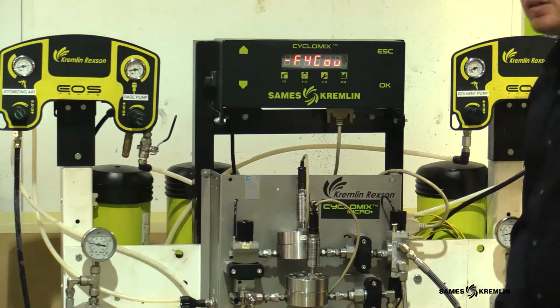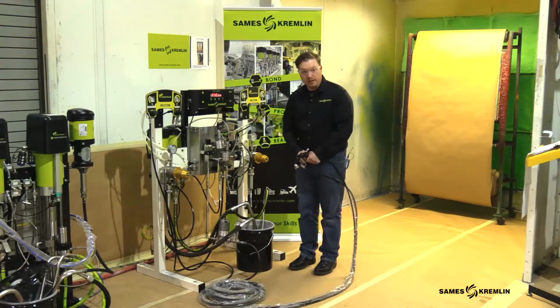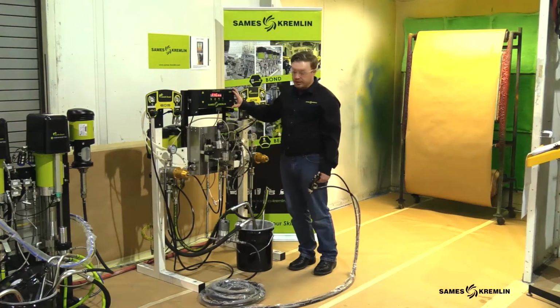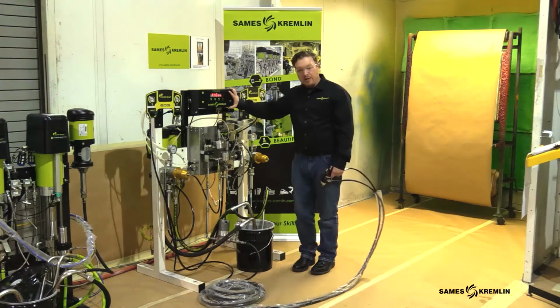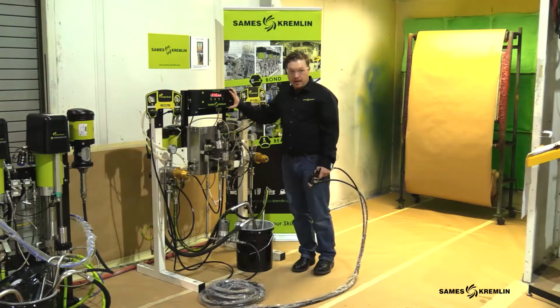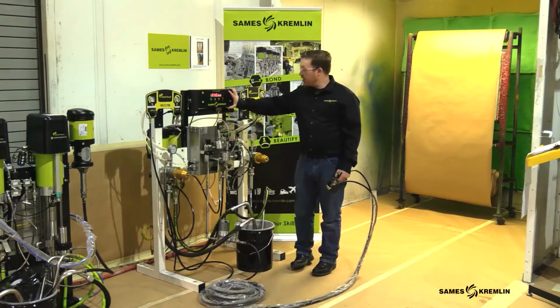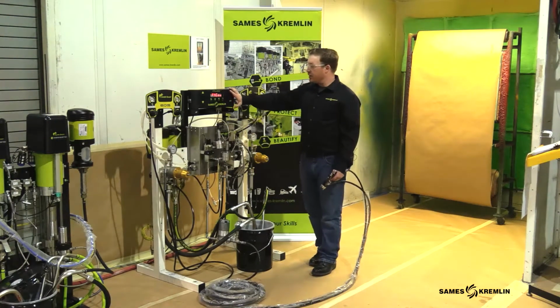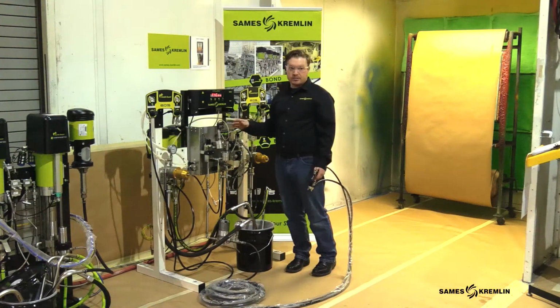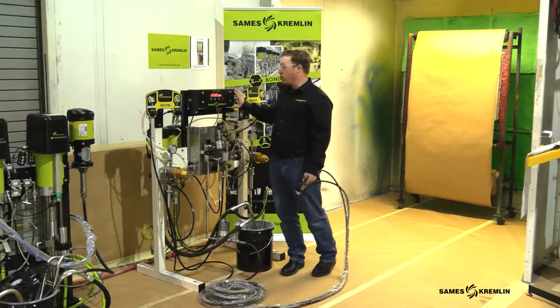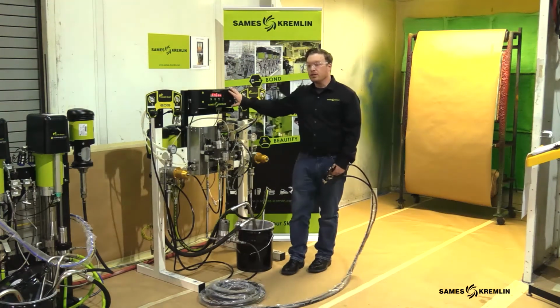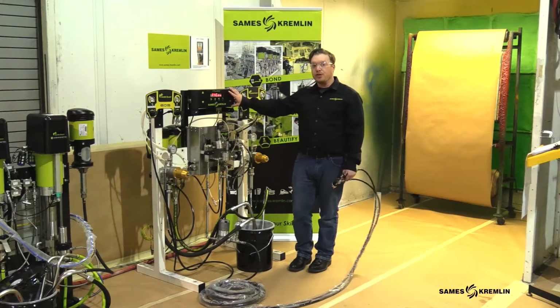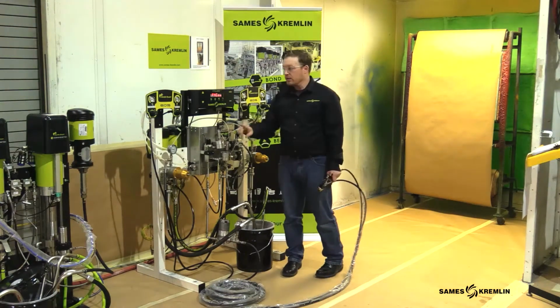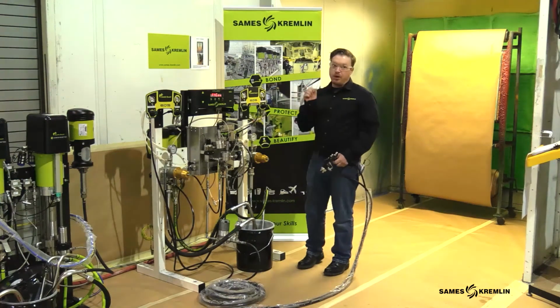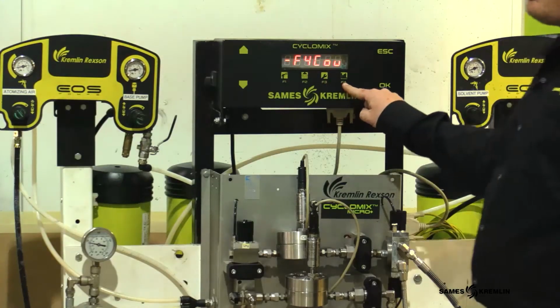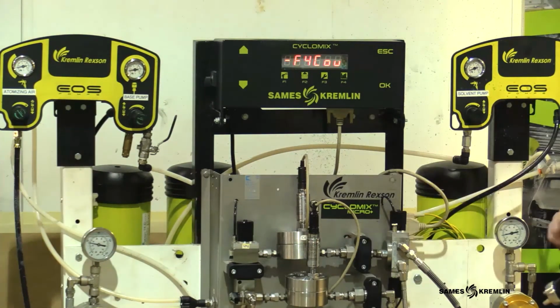We have also developed a data link networking system that is specific to this machine. It consists of a 4-conductor telecom wire, a solid core telecom communication cable. We use a simple node address system to designate from one machine to the next, and we're capable of connecting up to 30 machines on one of these networks. That prevents anybody from having to come to the F4 menu and write down those values.